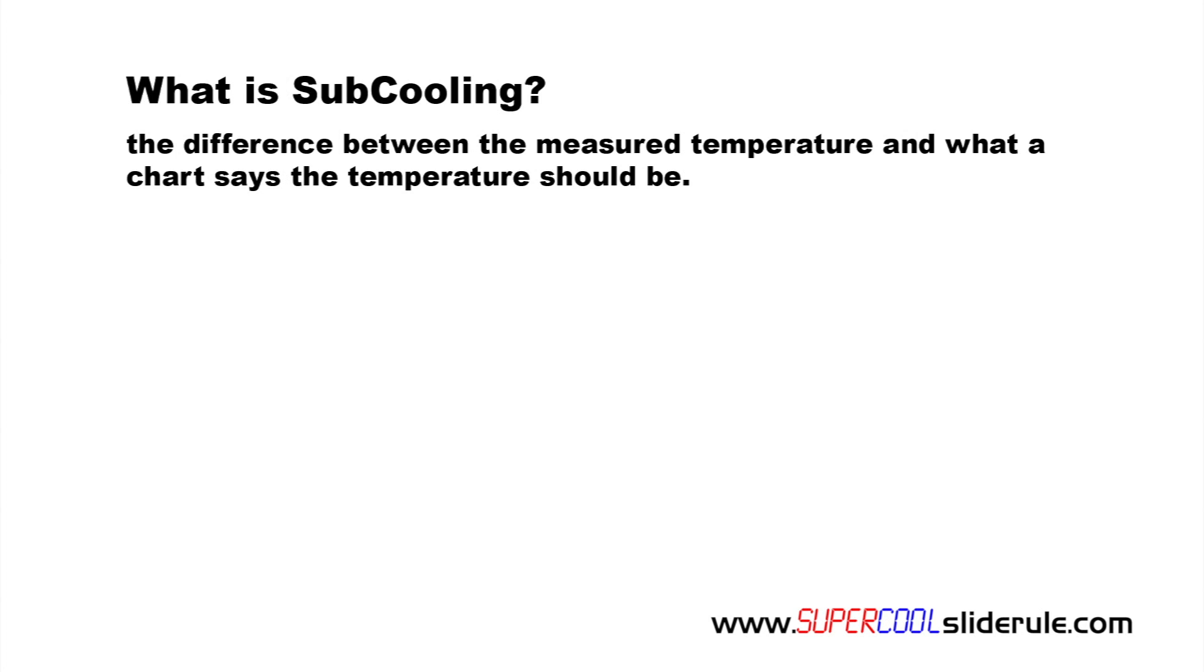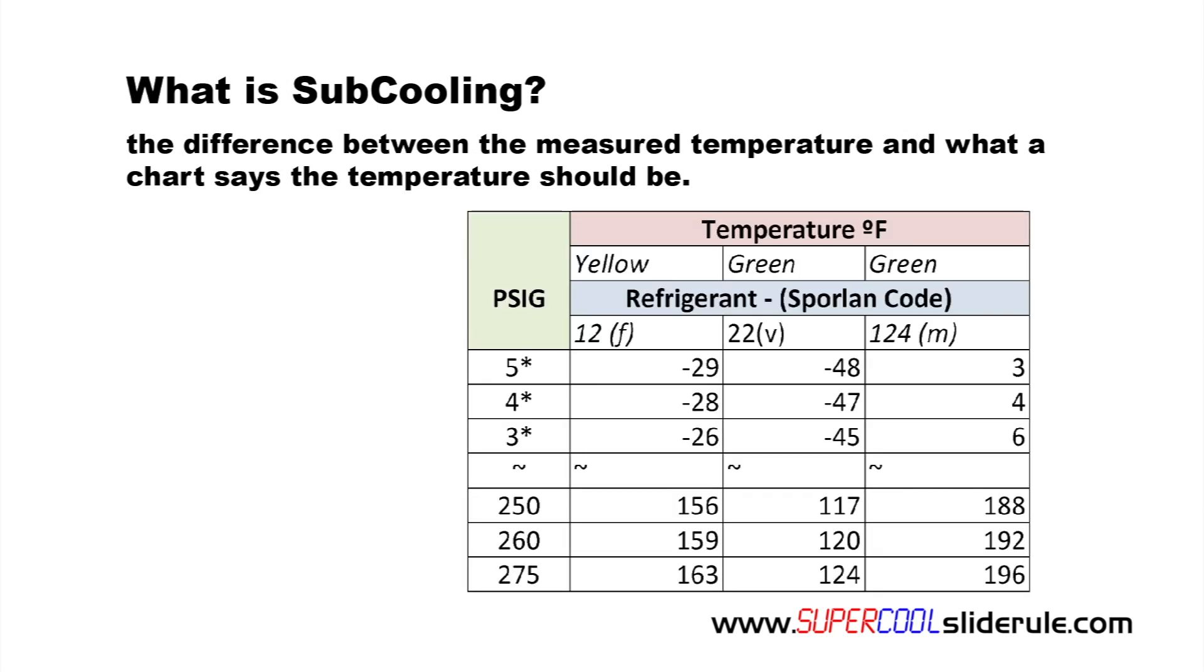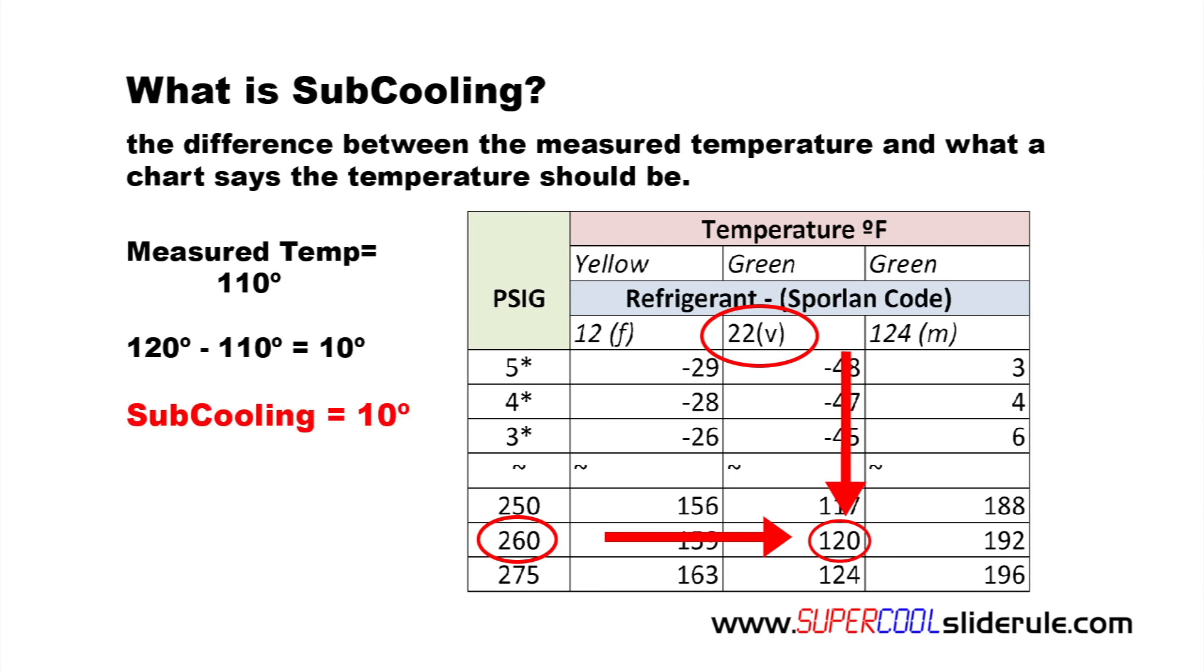Subcooling is simply the difference between the measured temperature and what a chart says the temperature should be. Here is an example. If we reference a temperature chart for R22, we will note that at 260 PSIG, our temperature should be 120 degrees. If we measure the temperature of the refrigeration liquid line and it is actually 110 degrees, this is 10 degrees cooler than it should be, so our subcooling is 10 degrees. Believe it or not, it is that simple.